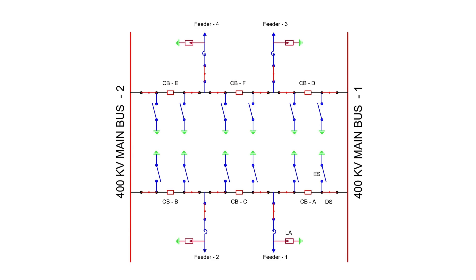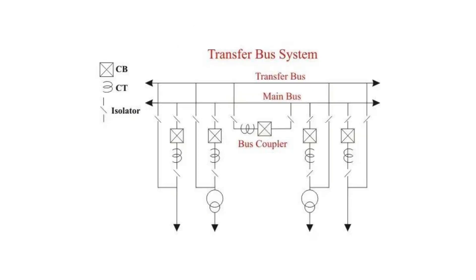Bus fault handling. In case of a bus fault, power to the connected feeders continues from the other bus. This avoids power interruptions required to isolate a faulty bus. In contrast, the two main and transfer bus scheme would trip all associated breakers during a bus fault, resulting in power supply interruption.